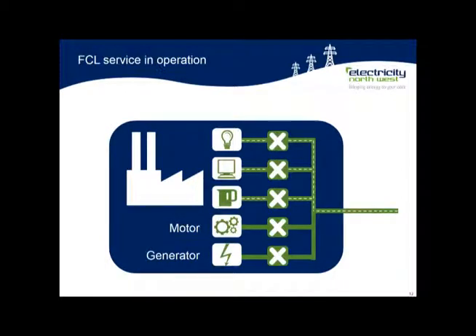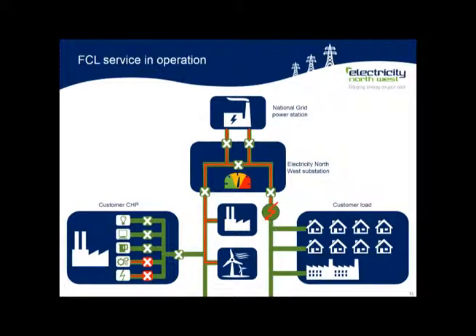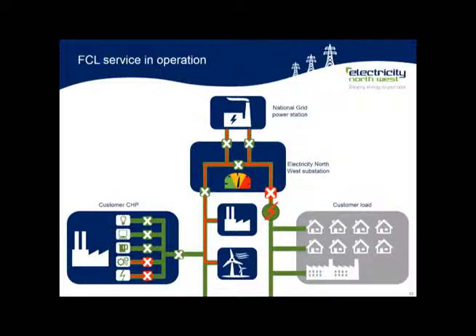Looking in more detail at the customer premises, you can still see the motor and generator are disconnected, removing the fault current from the network. But the supplies for light, heating and other uses are unaffected by this change. Now that the fault current has been reduced, the circuit breaker can operate safely. The fault is isolated as before and the customers on the right of the diagram go off supply. The rest of the network returns to normal and the circuit breakers at the CHP can be reclosed. All of this, from fault to reclosure, can happen in a matter of minutes.